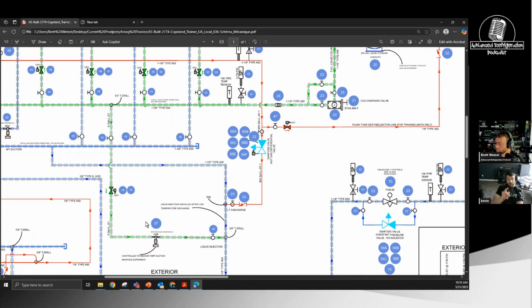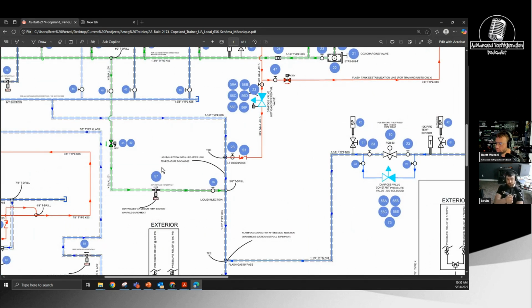And then we have liquid injection going into that medium temp line where it's dumping in. So we had a stepper, not a solenoid. We had a solenoid controlling the inlet to it and then a stepper injecting into it off of a calculation of superheat. For a failsafe. For a failsafe. No, but I'm saying the solenoid's there for a failsafe. So if God forbid it would stop, the rack would just shut down. At least this would de-energize. Correct. I'm assuming all these solenoids de-energized if there were no compressors running. Yeah. If the medium temp pumps shut down, then it de-energized the circuits. Makes sense. So it was looking at the proofs.